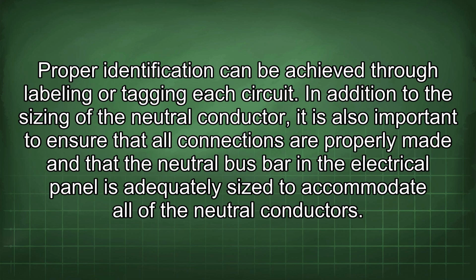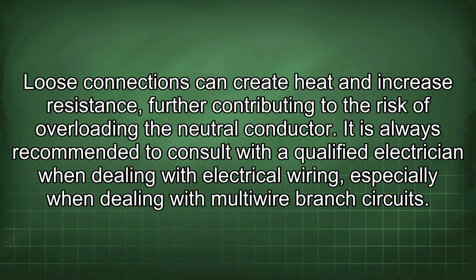In addition to the sizing of the neutral conductor, it is also important to ensure that all connections are properly made and that the neutral busbar in the electrical panel is adequately sized to accommodate all of the neutral conductors. Loose connections can create heat and increase resistance, further contributing to the risk of overloading the neutral conductor.